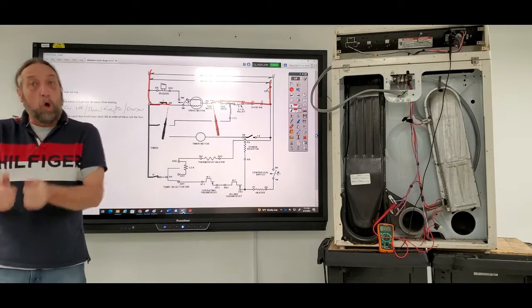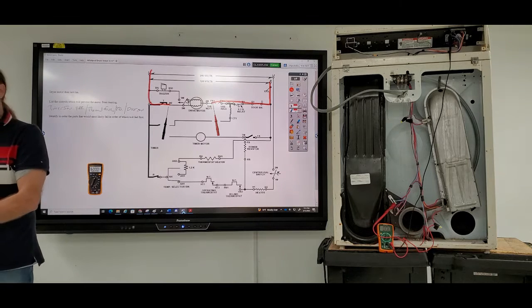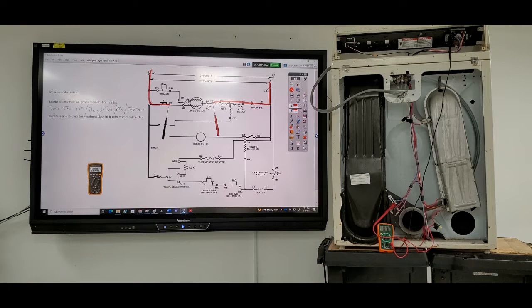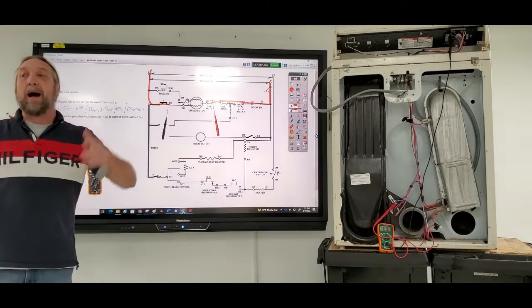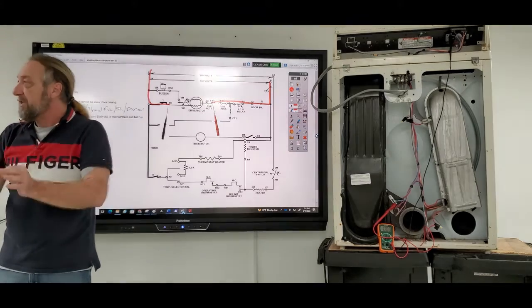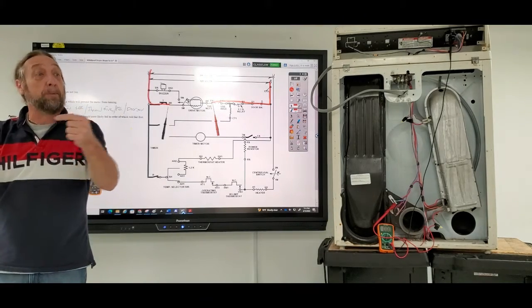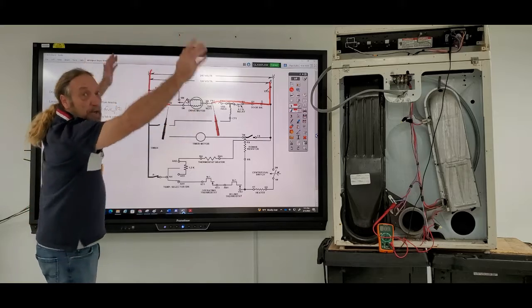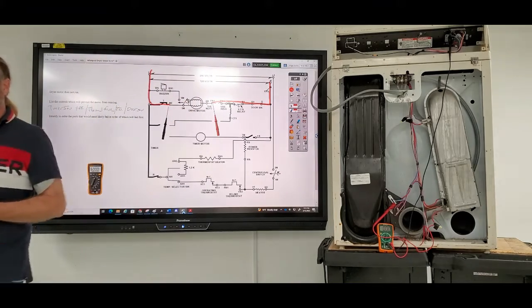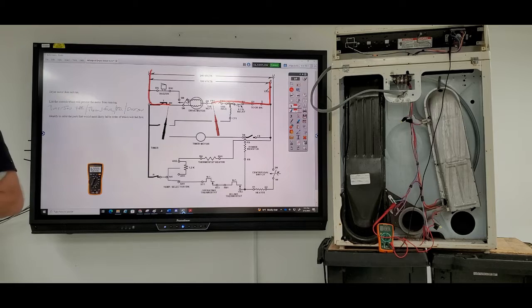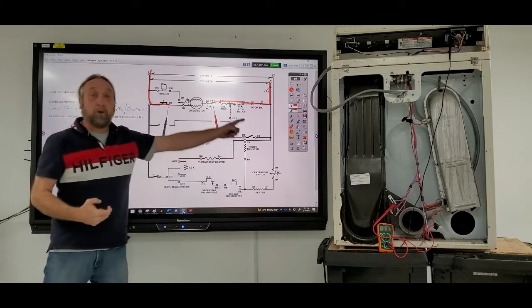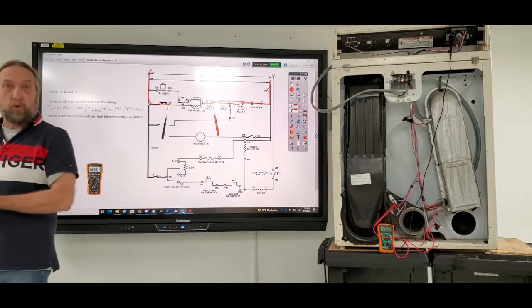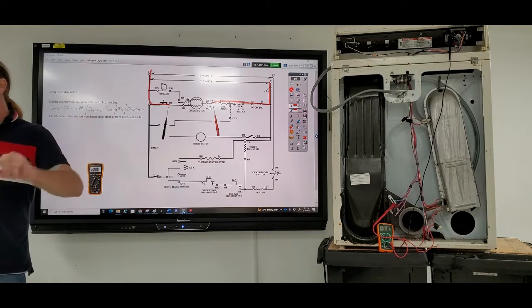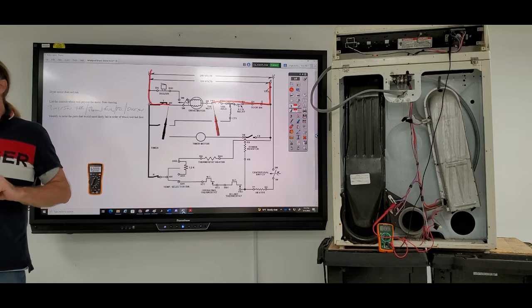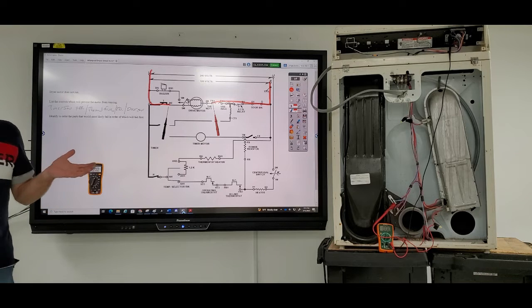Is that faster than ohming out the door switch, ohming out the timer, ohming out the start switch, ohming out the fuse? Yeah, you can ohm them out. There's nothing wrong with that. Time-wise, I've just checked the circuit. Voltage testing is not checking what's in between the meter leads. It's checking the circuit up to those meter leads. It's telling me where the voltage is. So I know that every one of those components are good. If I did not have voltage, something's broken on either side, and we'll talk about that in a second. But one voltage test just eliminated 5 parts for me to test.